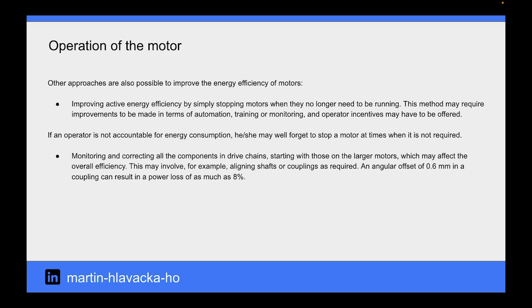Monitoring and correcting all the components in drive chains, starting with those on the larger motors, which may affect the overall efficiency. This may involve, for example, aligning shafts or couplings as required. An angular offset of 0.6 mm in a coupling can result in a power loss of as much as 8%.